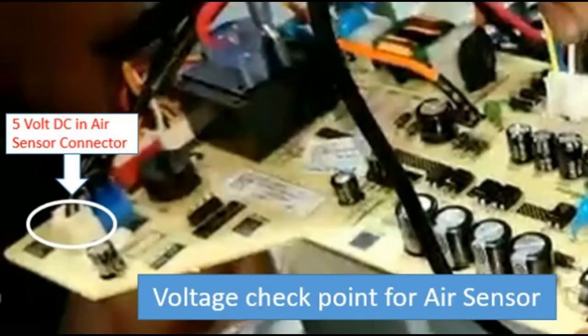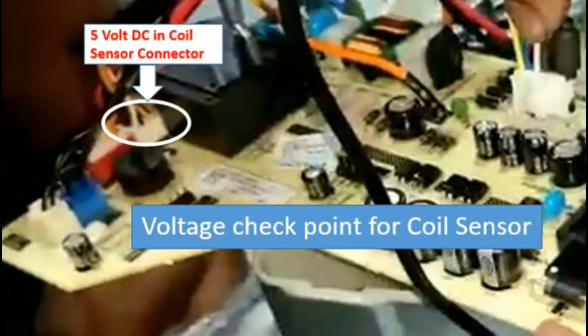For checking the air sensor, we have to check 5 volt DC in the sensor jack pins. If 5 volt DC is coming, then the PCB is okay. If the 5 volt DC is not available, then the defect is in the PCB. For the coil sensor as well, we have to check the 5 volt DC. It has to be available. If it is not there, then the problem is again in the PCB.